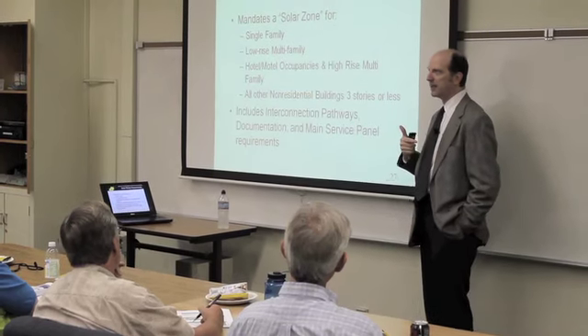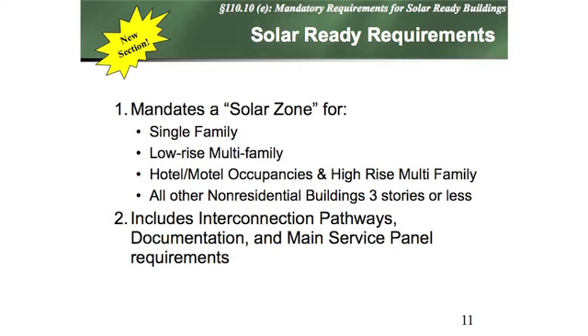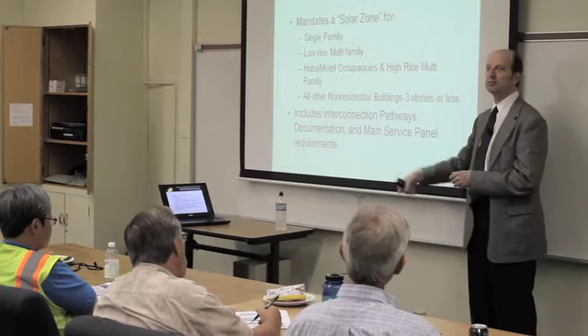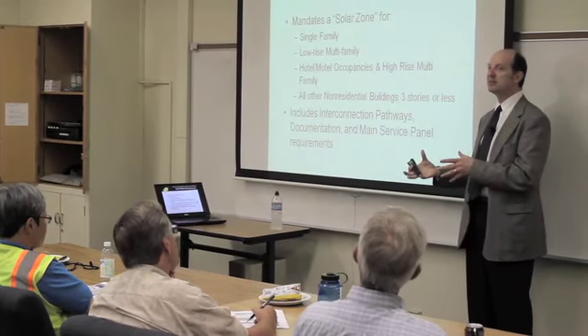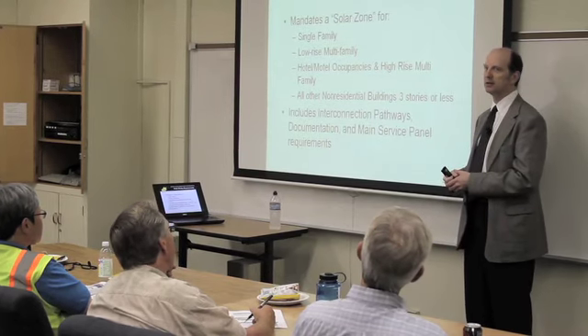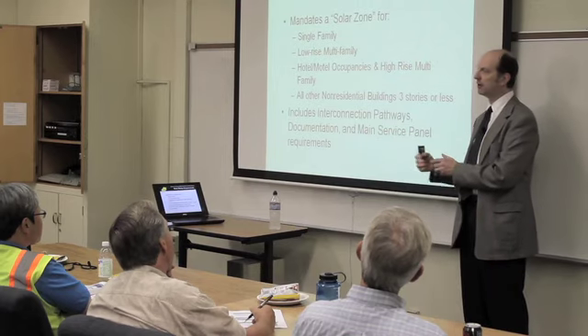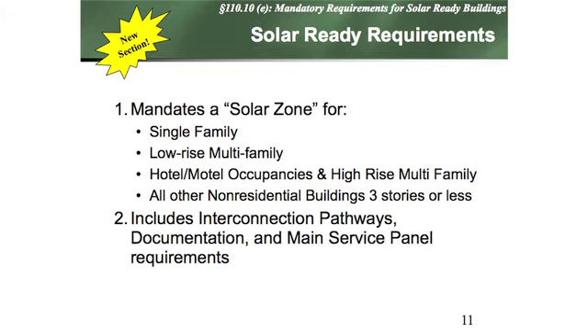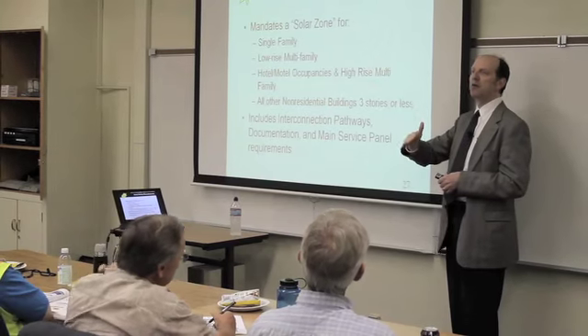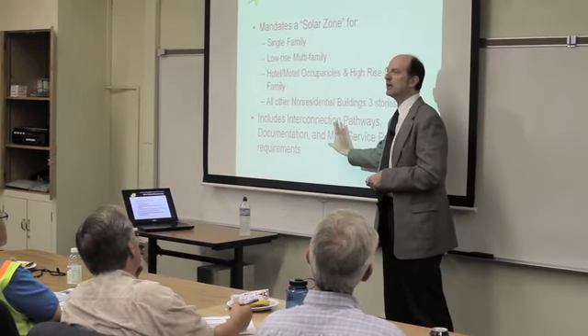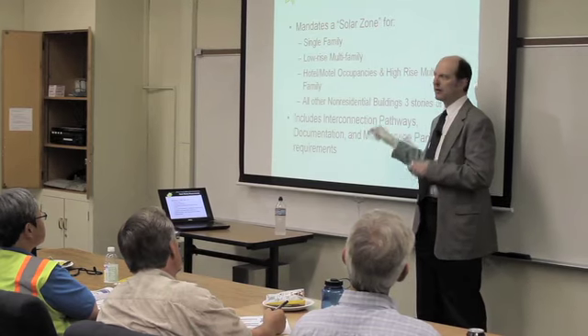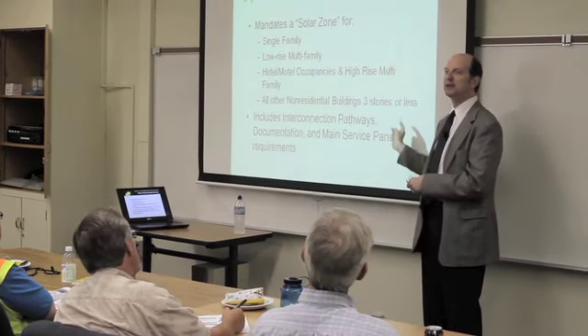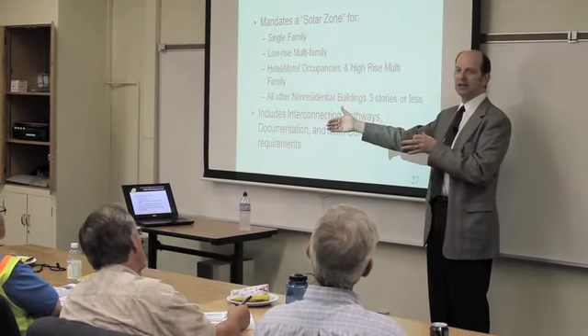One thing I like to point out is how the code folks think. Sometimes you can't put something in the code today, even though you want to—a perfect example is they'd love to tell you to put photovoltaics on every roof, but there's not a payback that meets the code's 15-year requirement, so they can't mandate it. What they can do is get you ready for it. There's a section, early in 110, that says for any new building you need a roof space set aside with no shadows overlaying it and no penetrations from below, so in the future you can add photovoltaics to that roof.